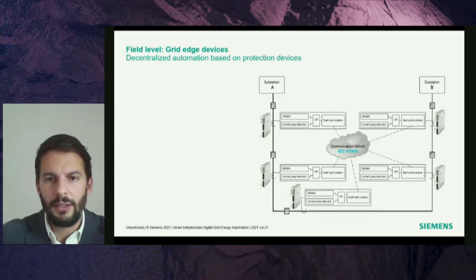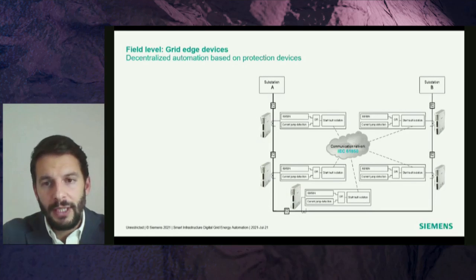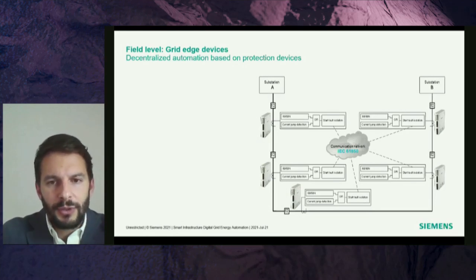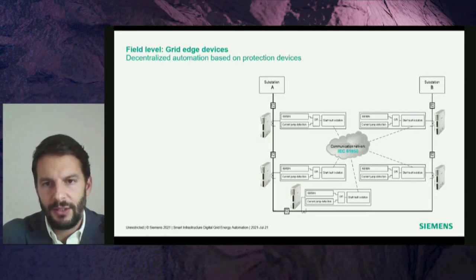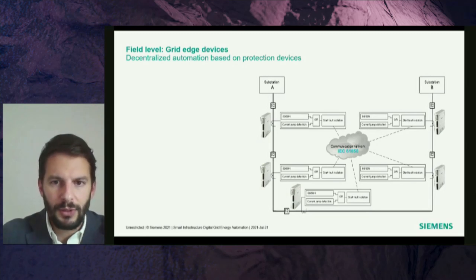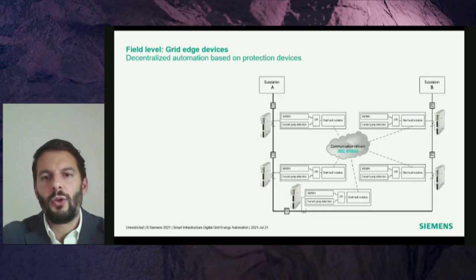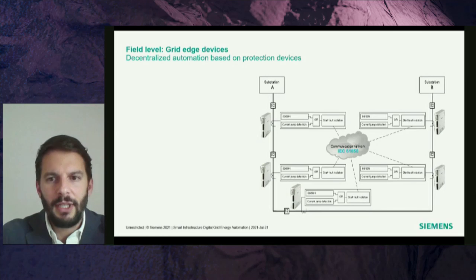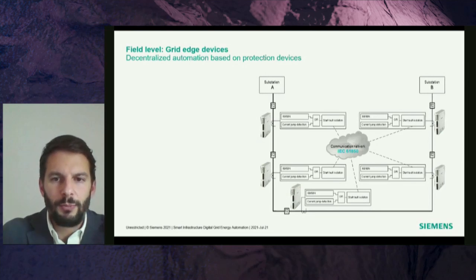For this purpose, as you can see also here from the picture, a communication network is set up in accordance with the state-of-the-art IEC 61850, a communication standard for energy automation. Supported by the standard, and that's a very relevant feature that the standard supports, a field device can multicast messages to all the other devices present in the same network, allowing them, therefore, to decide whether or not to discard its content. The main advantage relates specifically to the speed of that communication and the reliability of the automation process. That's one important part of the system implementation.